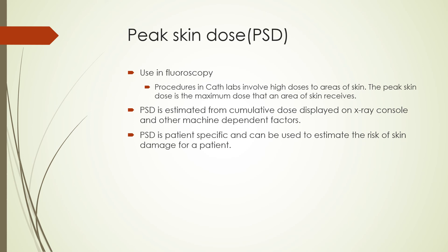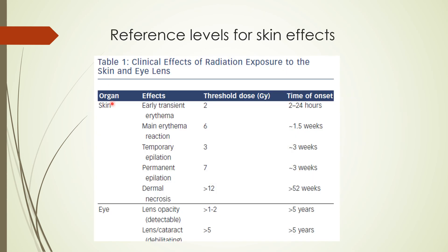For deterministic effects such as skin damage, we can use the peak skin dose, or PSD. For patients who undergo procedures in the cath labs because of high doses involved, we typically want to calculate the peak skin dose for that patient. Peak skin dose is a deterministic effect that has a threshold for the effect to occur. It is calculated from cumulative dose displayed on the imaging console as well as various correction factors applied to the displayed dose. Peak skin dose is patient-specific and is used to estimate the risk of skin damage to the patient. This table shows various threshold doses for different skin effects to occur. These threshold doses are applicable to patient doses particularly in the interventional suites. Note that the dose unit used for deterministic effects is milligray or gray.